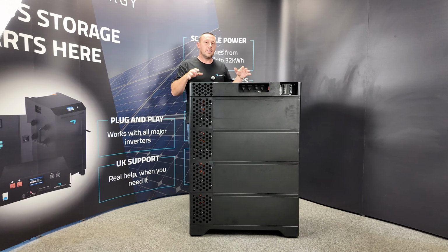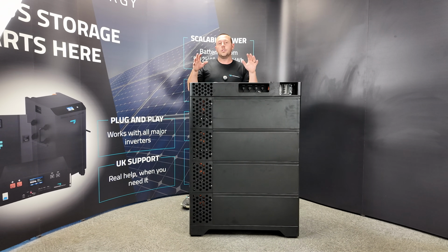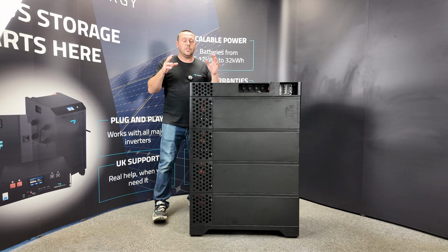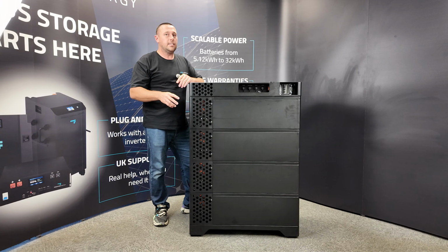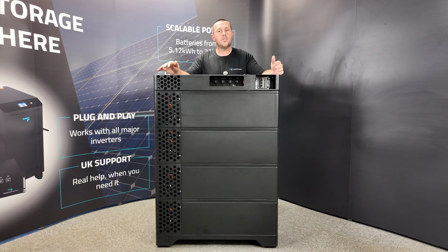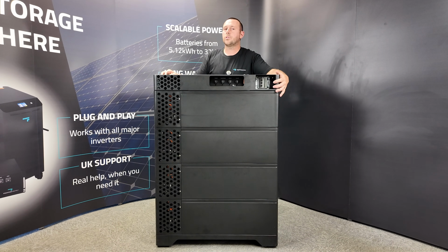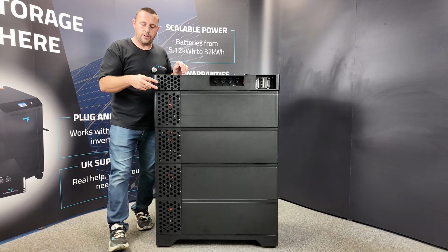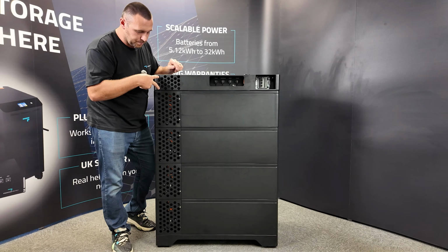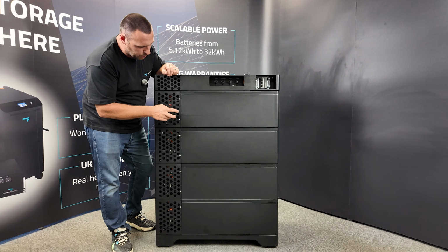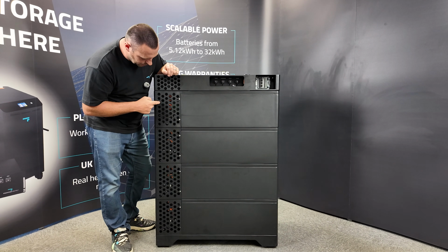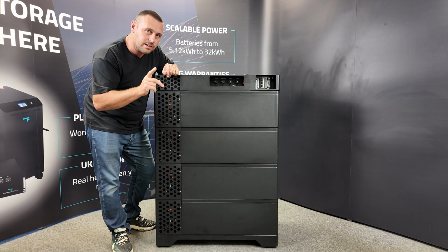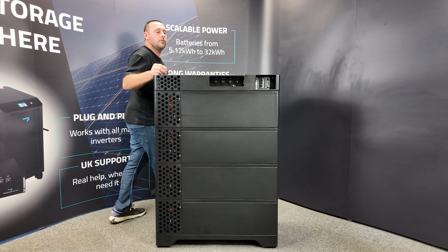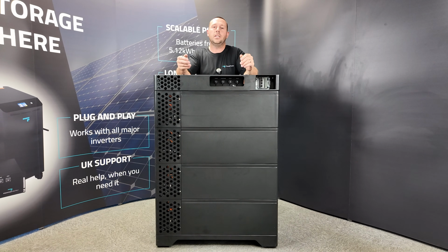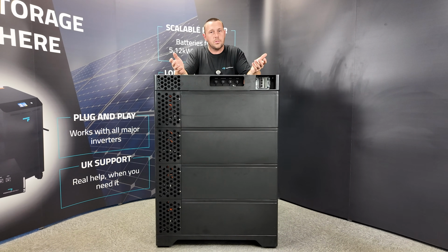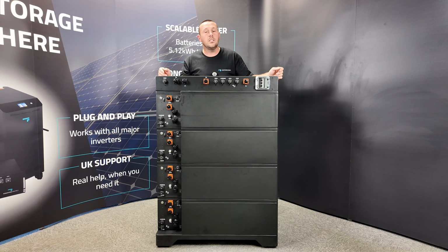All jokes aside, this does now weigh over half a ton. So if you're putting it into a house or somewhere, you need to make sure that the floor is rated for this amount of weight. To undo the covers for the cables, there are 2 Phillips screws on this side and then 2 further Phillips screws buried inside here. For the panels on the battery module, there are Allen screws here, and again, 2 further ones inside here. You will need an extension to get to those. However, I'm sure you have seen enough of me doing screws in this video, so let's just jump to the next bit. That was easy, wasn't it?